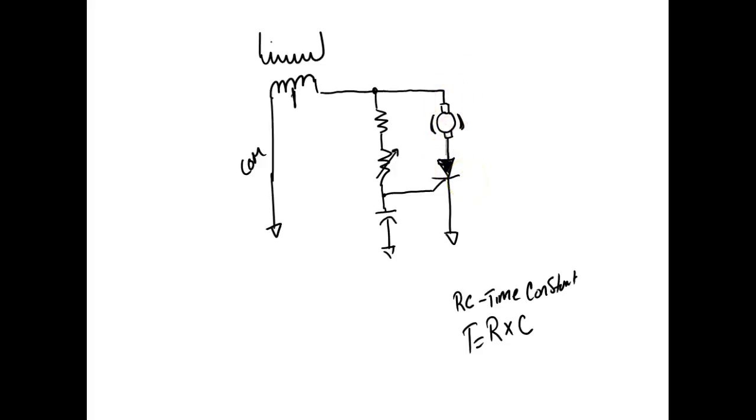Now, DC motors had the advantage for years as being very easy to control. AC motors are real hard to control the speed. For one thing, we're putting AC on them. And on an AC motor, the motor tries to rotate, it never hits this for reasons we know. It's 120 times the frequency divided by the number of magnetic poles that we have.